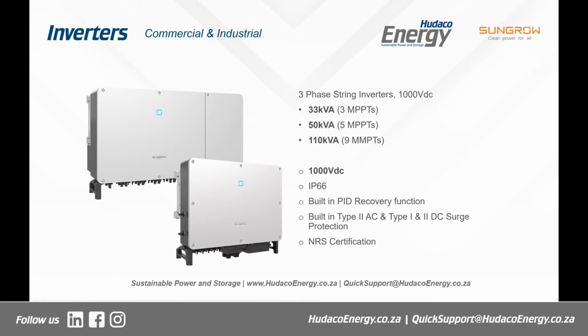And your AC output is 400 volts. You take these, you put them into an AC combiner with some protection, with some switchgear, and you feed straight into the building's reticulation. For Southern Africa, we only bring in the premium model. The difference between the base and the premium is we have type 1 and type 2 DC surge protection built in. That comes standard in the price. You do not have to go and add additional combiner boxes outside. In fact, you can run your modules and you can plug them straight into your MPPT inputs.